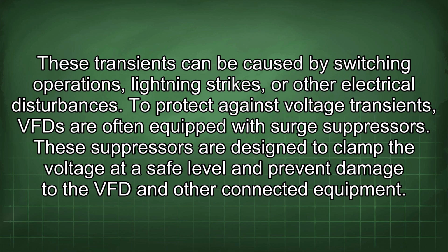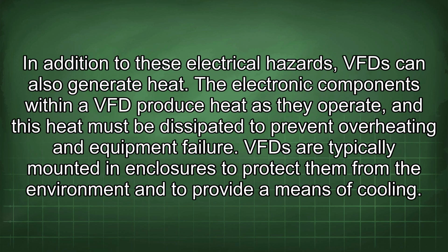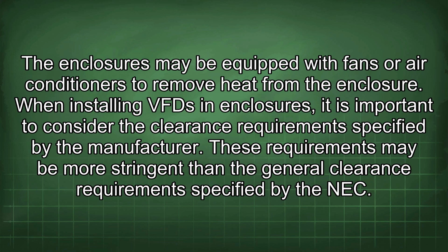connected equipment. In addition to these electrical hazards, VFDs can also generate heat. The electronic components within a VFD produce heat as they operate, and this heat must be dissipated to prevent overheating and equipment failure. VFDs are typically mounted in enclosures to protect them from the environment and to provide a means of cooling. The enclosures may be equipped with fans or air conditioners to remove heat from the enclosure.